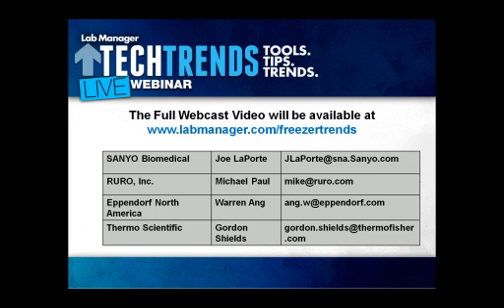This is Joe at Sanyo. The energy consumption that we've seen traditionally on water-cooled freezers, and in Europe, they're, at least from our perspective, much more popular than they are in North America, although there is some ground being gained on that here. We're finding that there is better energy consumption on the freezer with a water-cooled freezer than we will with a standard air-cooled freezer.